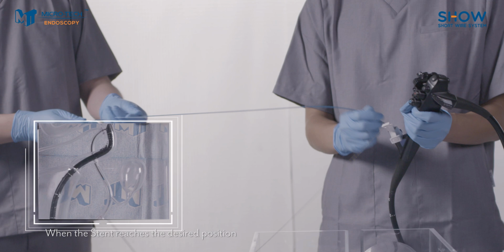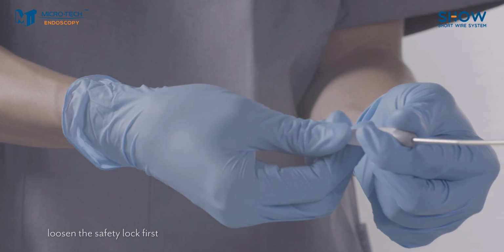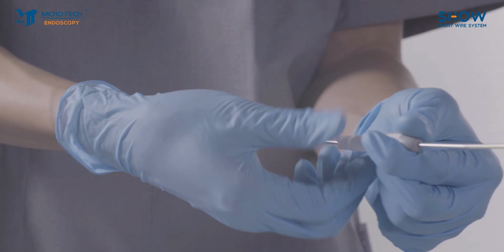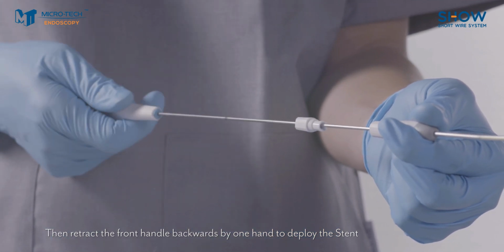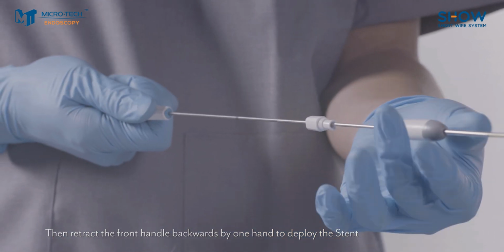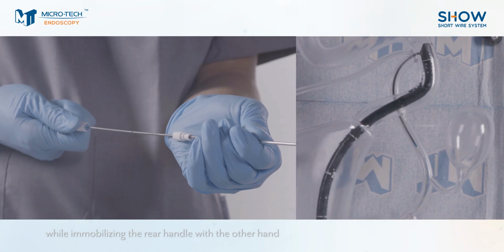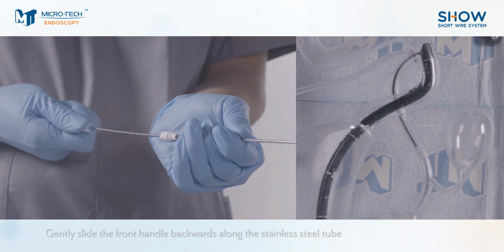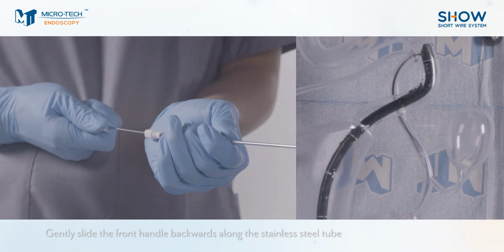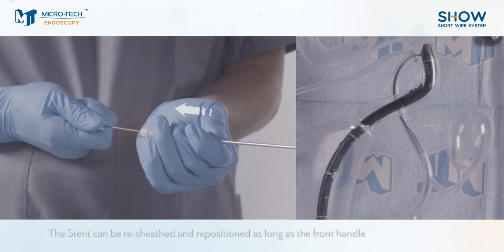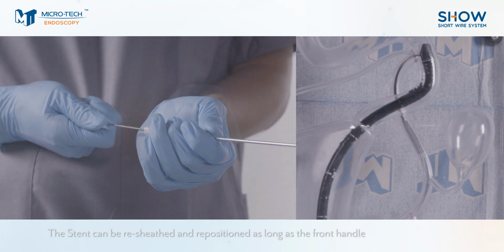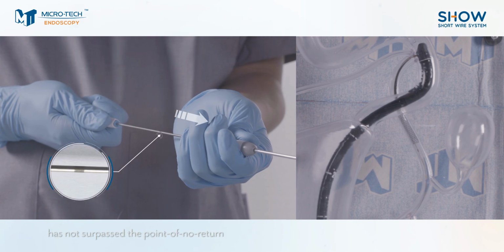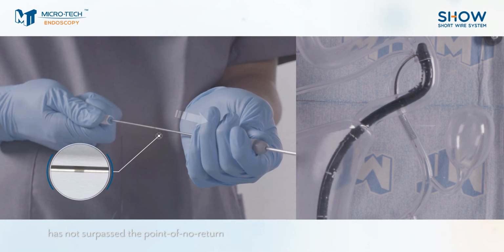When the stent reaches the desired position, loosen the safety lock first. Then retract the front handle backwards by one hand to deploy the stent while immobilizing the rear handle with the other hand. Gently slide the front handle backwards along the stainless steel tube. The stent can then be resheathed and repositioned as long as the front handle has not surpassed the point of no return, shown as a black ring marker on the applicator.